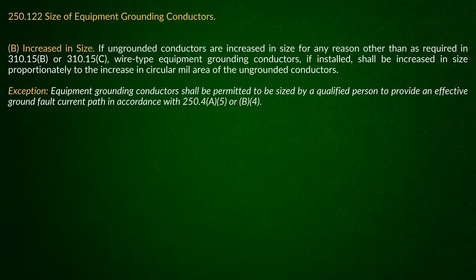And that's why we go over this stuff, to show, because when you go in and you look at 250.122B, if you look at this and you just read the last part of it, it says, if installed, it shall be increased in size proportionally to the increase in circular mil area of what? The ungrounded conductors. Yeah. Now why is that? Because the equipment ground is sized based off what? The overcurrent protection device. It has nothing to do with the conductors.